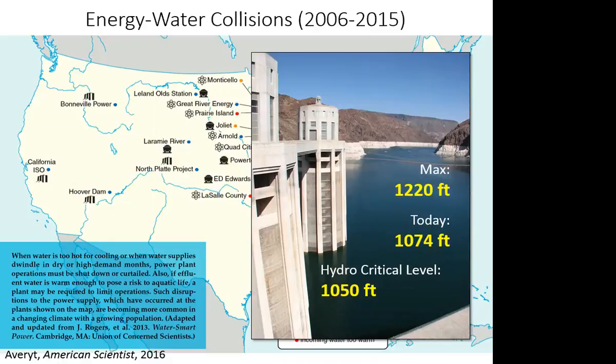This is Lake Mead on Hoover Dam, a picture I took last summer. Maximum elevation is 1,220 feet. As of yesterday, the elevation at Lake Mead was 1,074. For every foot Lake Mead drops, you lose 5.7 megawatts of capacity. Right now Hoover Dam is only operating at about 23% of its potential. This is really important because even at only 23 to 25% of potential, Hoover Dam provides about 80% of all the peaking power for all eight western, southwestern states. So that's something to really keep in mind.